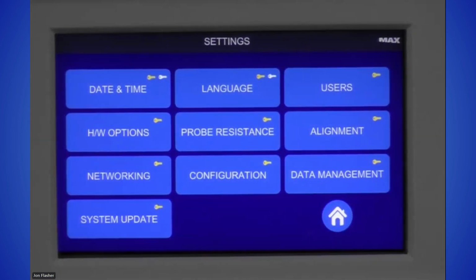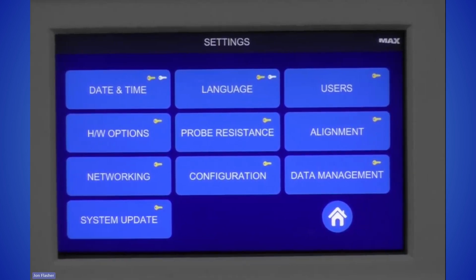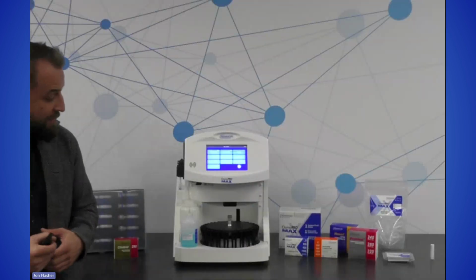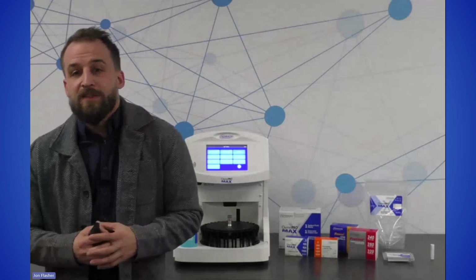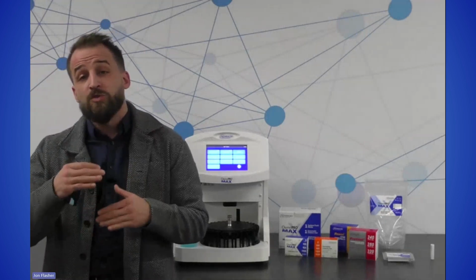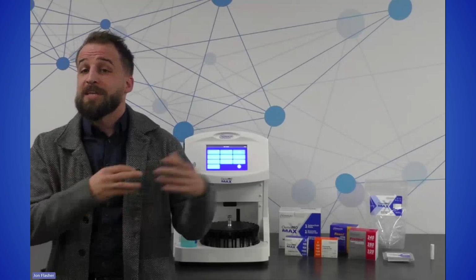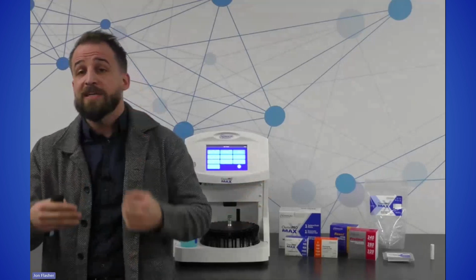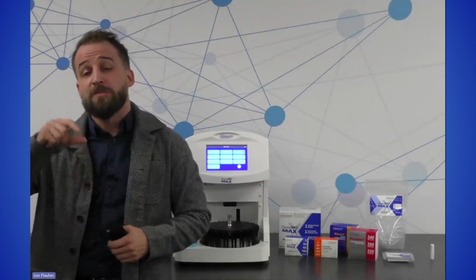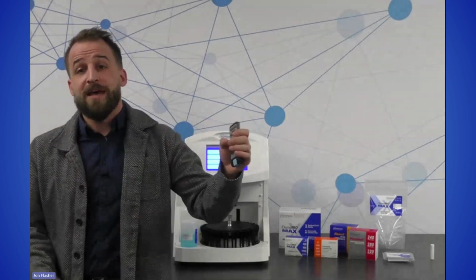Okay, so I did want to mention for that daily Clinitrol 290 check that you're going to be programming for 7 a.m. or whatever you want to program it for at the beginning of each day. The reason that's required is because it's actually checking your daily Clinitrol 290 performance against a 290 baseline that's established at the time of calibration. So every single day, when you run the test, the instrument is comparing your result to the baseline established.